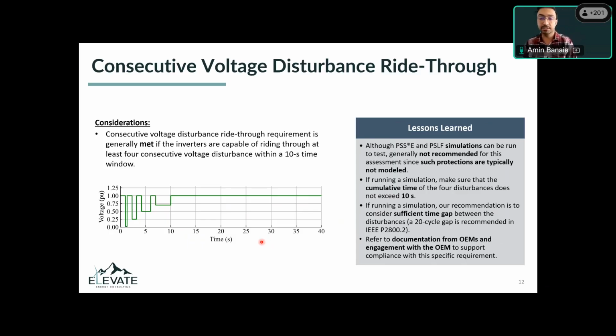And finally, the last requirement, which is not an official requirement of PRC-29, but it's included in, I think, item 8 of attachment 1 of the standard, says that the IBR is allowed to trip for more than 4 consecutive voltage disturbances. So how we see it is that it's not allowed to trip for 4 or fewer voltage disturbances. So we have a specific test case for this one as well. And this is the curve that we apply at POM for this case.